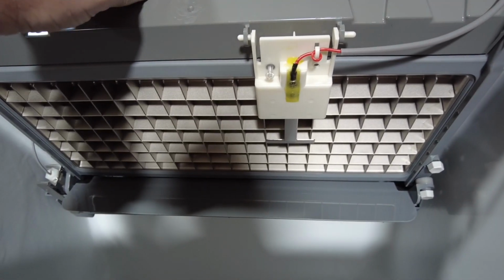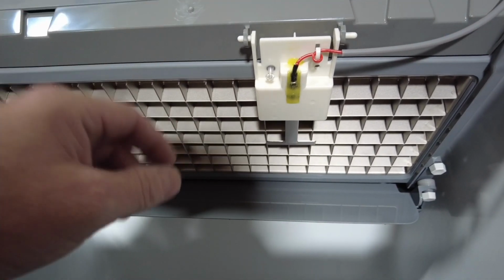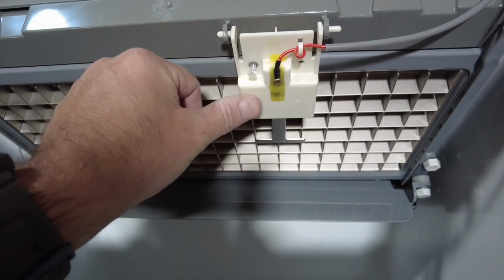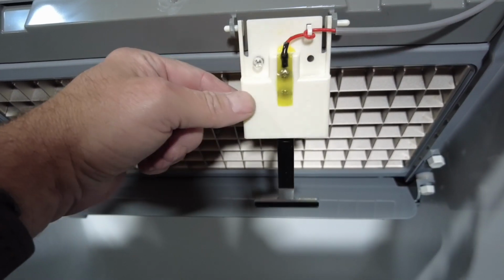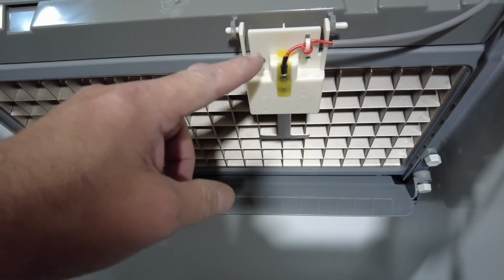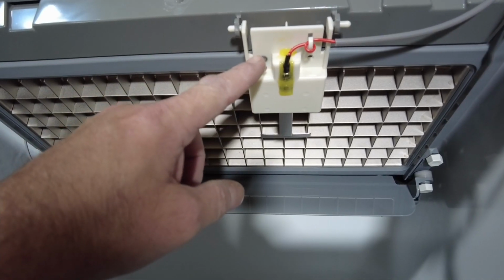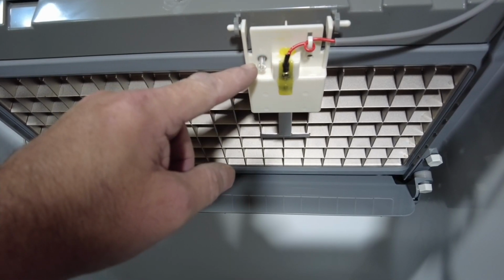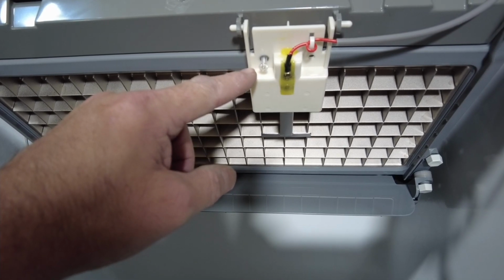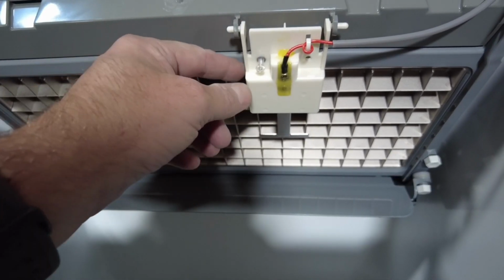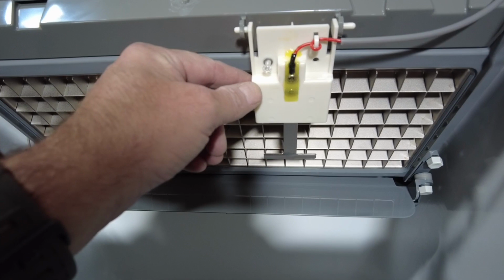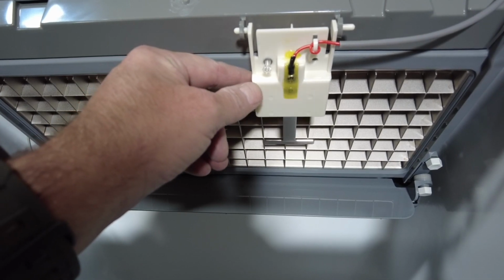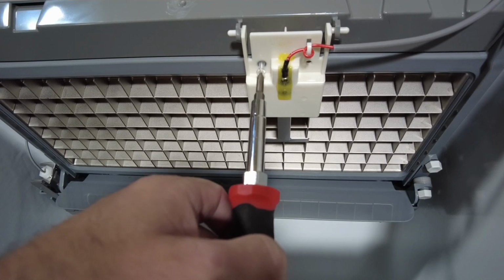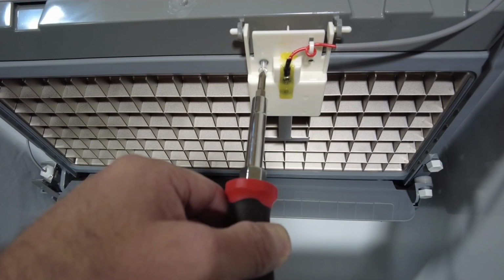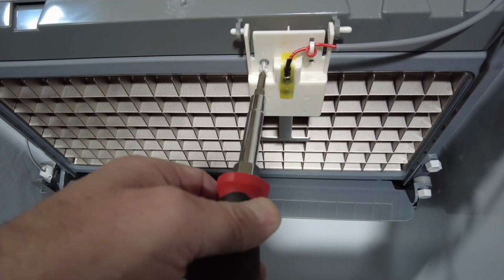So we're looking for a 1/8 bridge here, and we don't want the probe to be touching the plate. We don't want it to be too far away from the plate either. Now you can use this screw here to adjust that bridge thickness. Turning that screw clockwise pushes it further away, and turning it counterclockwise brings it closer to the plate.